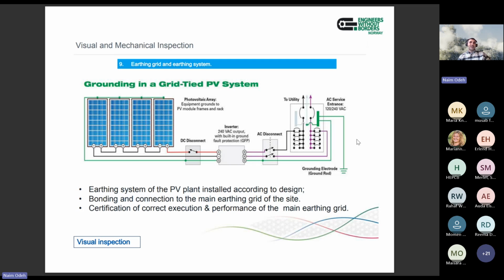Installing the earthing for a solar system is not difficult, actually. As you can see in this simple diagram, it is just connecting the frames and so on. But this has high impact if it is not followed. So earthing is very important, and it's important to check the modules one by one when you do an inspection, that the connection for earthing is already there.